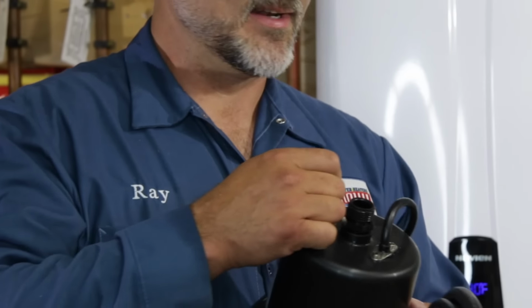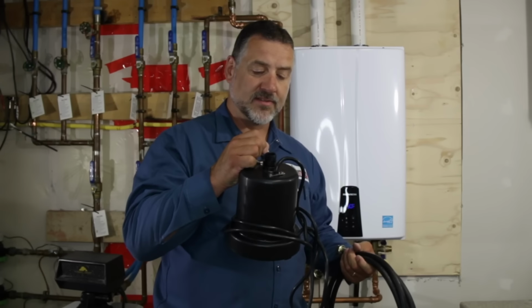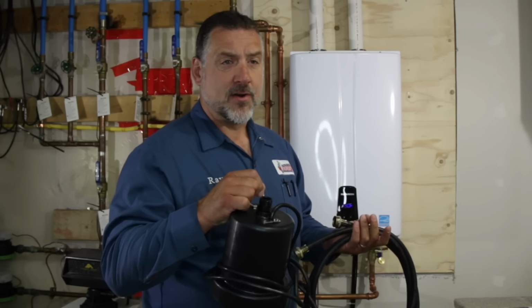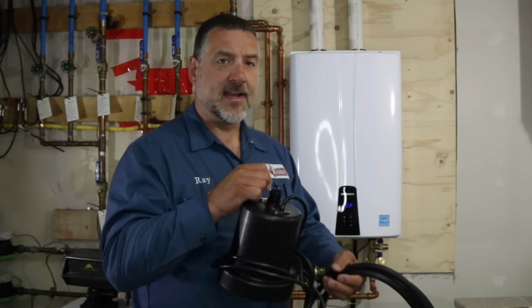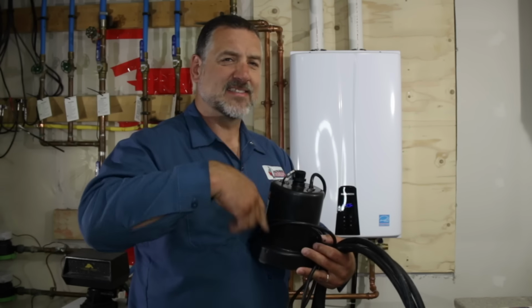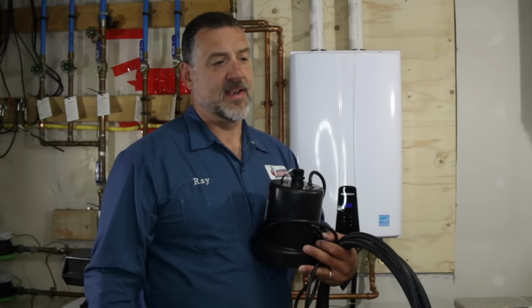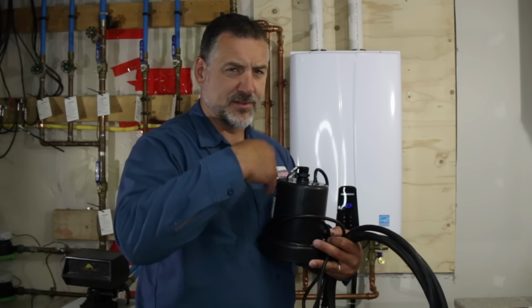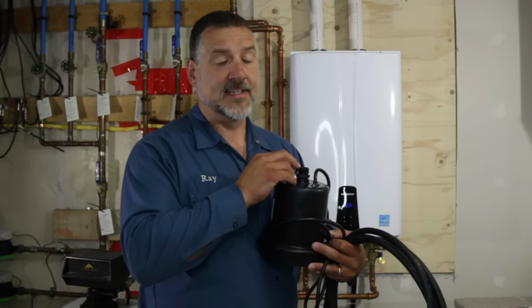You don't want a sump pump with a large 1.5 inch thread on it. Make sure it can connect directly with the hose, real low volume, maybe a 1/6 horse or 1/5 horse pump. If the vinegar goes through slowly it can descale properly, you don't want something like a 1/2 horse that pushes through so fast it doesn't actually descale the heater.